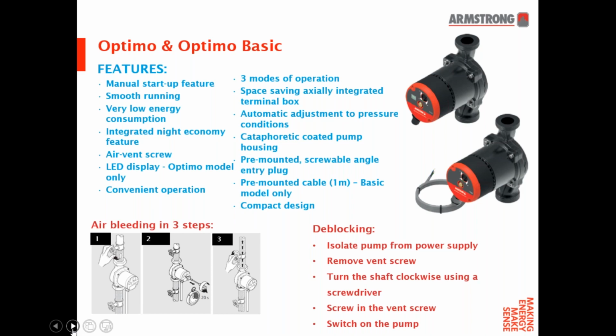The Optimo, but not the Optimo Basic, has an LED display. It's convenient operation, and it has three modes of operation. There's a potentiometer on the front face, just slightly above the air vent screw, where once you've turned the potentiometer, you can select either proportional pressure, fixed speed, or constant pressure. The display to the left of the air vent screw indicates the power consumption in watts whilst the unit is running. To set up the circulator, when the potentiometer is turned initially, the display first indicates the mode of operation, then the value of set head in meters. After a while, it then reverts back to the power consumption and the symbol of the control mode permanently.